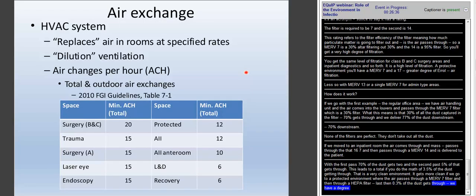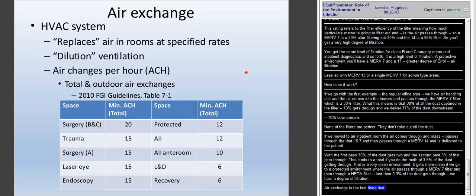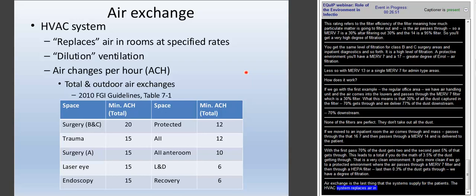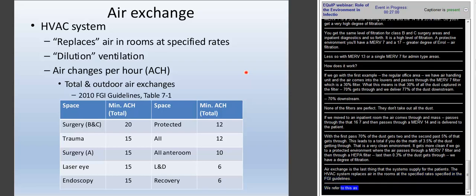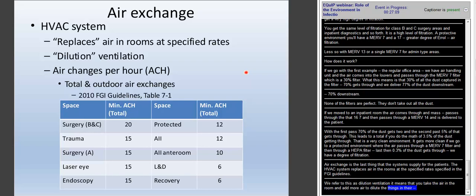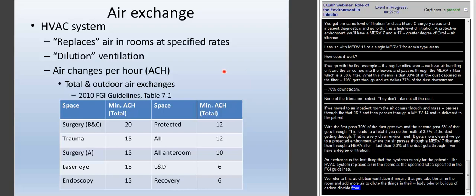Now, air exchange is the last bit that these systems supply to us for our patients. The HVAC system replaces, and I put that in quotes, replaces air in the rooms at specified rates as specified in the FGI guidelines. We refer to it in industrial hygiene circles as dilution ventilation. And quite simply, it means you're taking that air in the room and you're adding more air to dilute whatever odorants are in there, or body odor, or the buildup of carbon dioxide from people breathing in the air and exhaling in the room. So these are expressed in air changes per hour, or ACH.